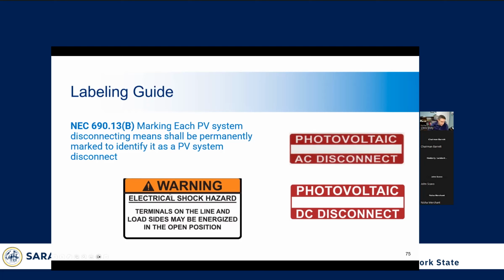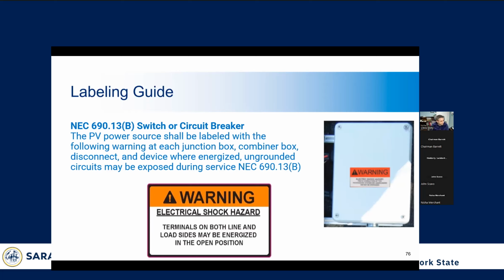You always need the electrical shock hazard label where there's potential for electrical shock. So that's an important one. And again, you have to make sure that the labels are suitable for the environment in which they're installed, so that they last the expected life of the system. Again, more about specific labels is the electrical shock hazard labeling. You want that on all your switches and circuit breaker panels, so that people understand that there's a hazard and to be careful.